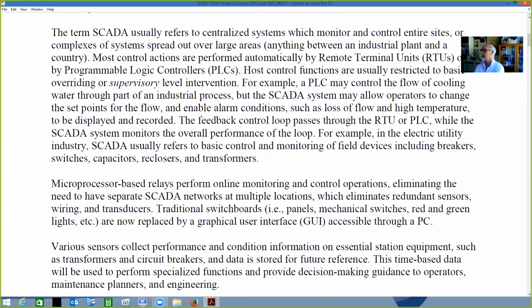For example, a PLC may control the flow of cooling water through part of an industrial process, but the SCADA system may allow operators to change the set points for the flow and enable alarm conditions such as loss of flow and high temperature to be displayed and recorded. The feedback control loop passes through the RTU or PLC, while the SCADA system monitors the overall performance of the loop.